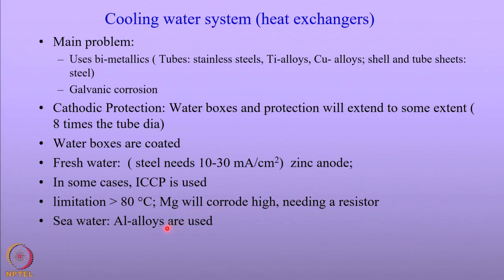The water boxes are generally coated, and for fresh water the current required lies in the range of 10 to 30 milliampere per centimeter square, and zinc anodes are generally used. However, if the temperature goes beyond 80 degrees Celsius, zinc anodes cannot be used and magnesium must be used. But magnesium corrodes very rapidly and needs a resistor to control the current delivered. In the case of seawater, aluminum alloys are used. Heat exchangers sometimes use the impressed current cathodic protection system as well, but it is better to use sacrificial anode systems as they are easier to maintain.